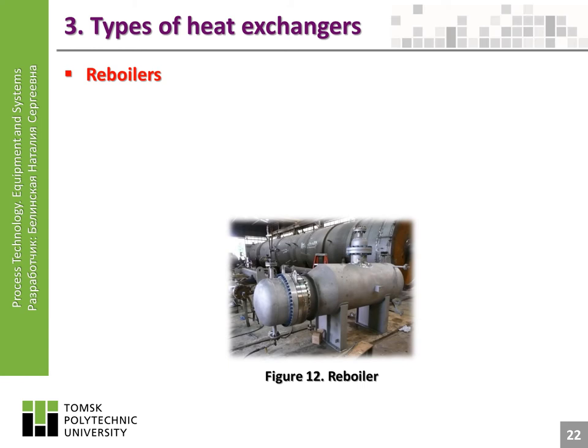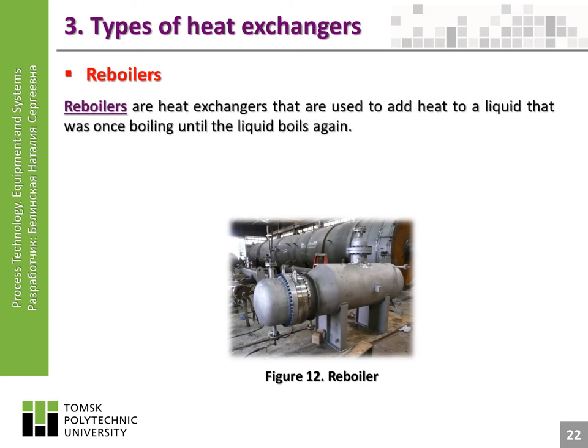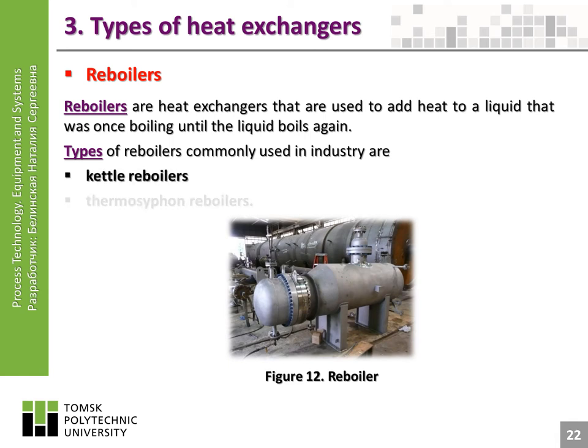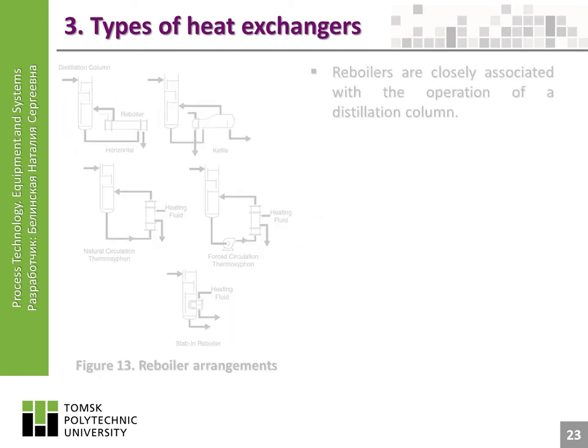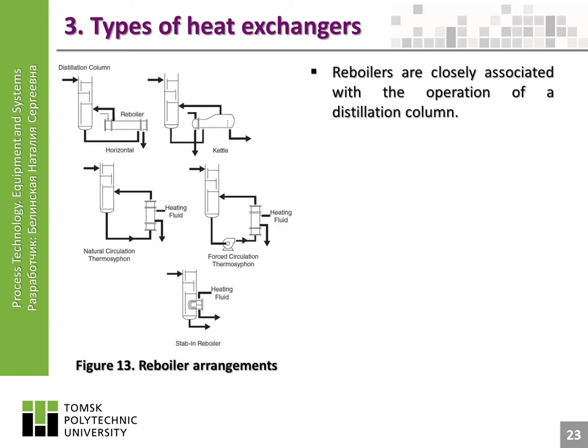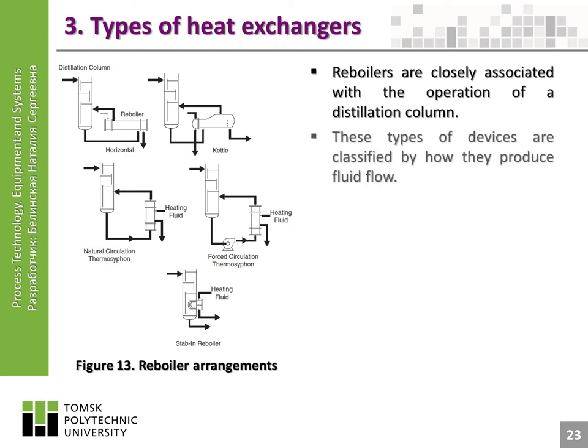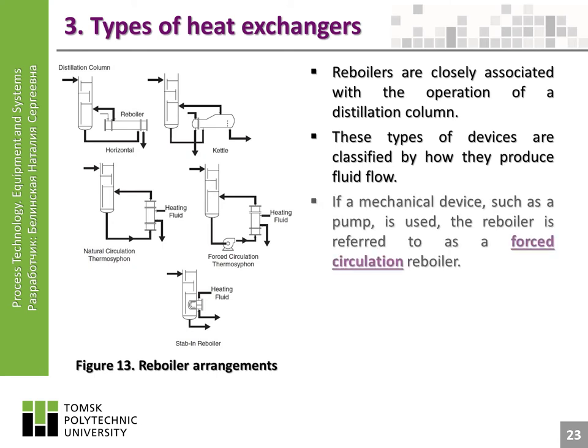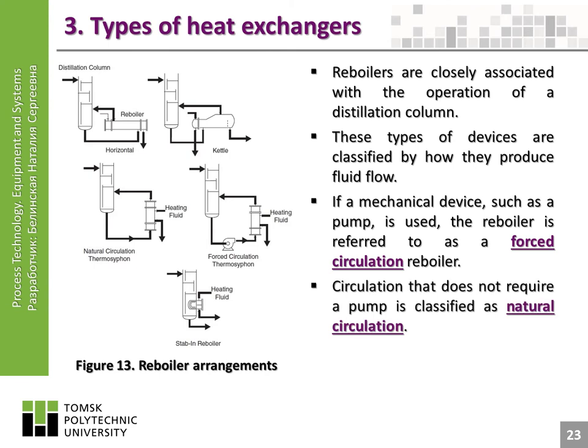Reboilers are heat exchangers used to add heat to a liquid that was once boiling until the liquid boils again. Types of reboilers commonly used in industry are kettle reboilers and thermosyphon reboilers. Reboilers are closely associated with the operation of a distillation column. These devices are classified by how they produce fluid flow. If a mechanical device such as a pump is used, the reboiler is referred to as a forced circulation reboiler. Circulation that does not require a pump is classified as natural circulation.